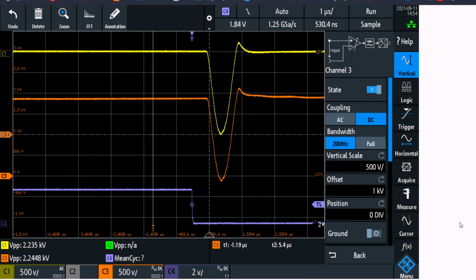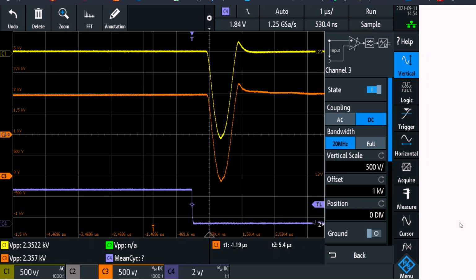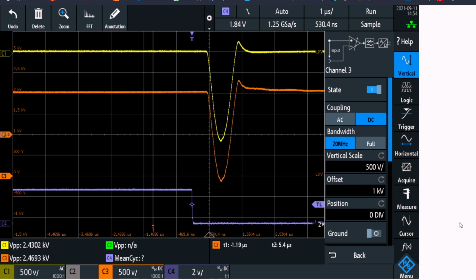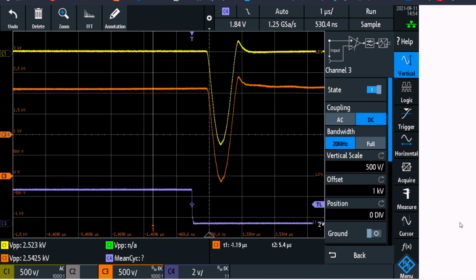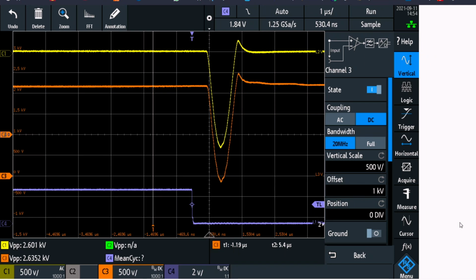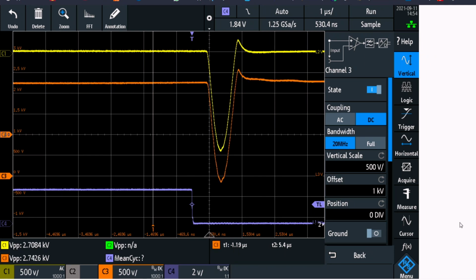Right now it's 2000 volts DC, as we have 4 divisions of 500 volts, and we can go higher, to 3000 volts DC, but I think I'll keep it like this. This is a good setting. We've got between 2 and 2.5 kilovolts inside the capacitor bank right now, and the impulses are around 1000 to 2000.